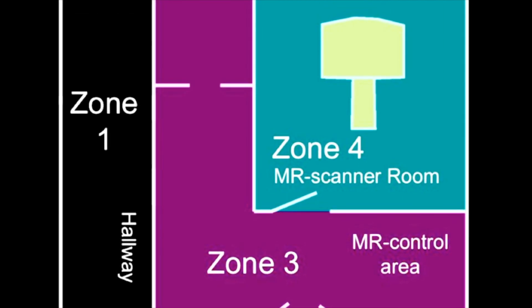The last zone is Zone 4. This is where the magnet is located. Access to Zone 4 should only be possible by passing through Zone 3. The walls of this magnet room are designed to contain the 5 Gauss line of the fringe field of the magnet. 5 Gauss is equivalent to 0.5 millitesla — we'll learn more about that later.